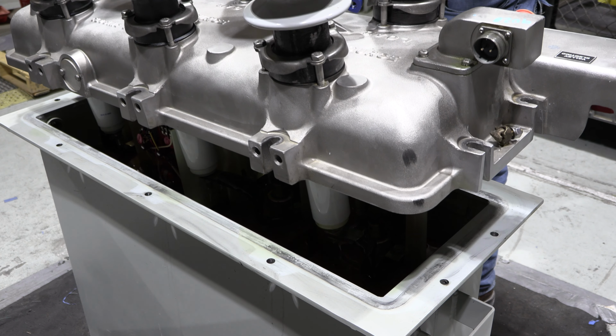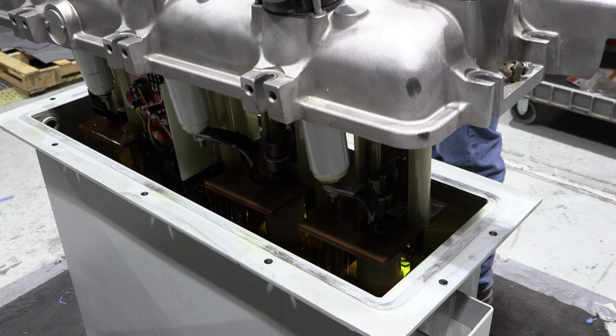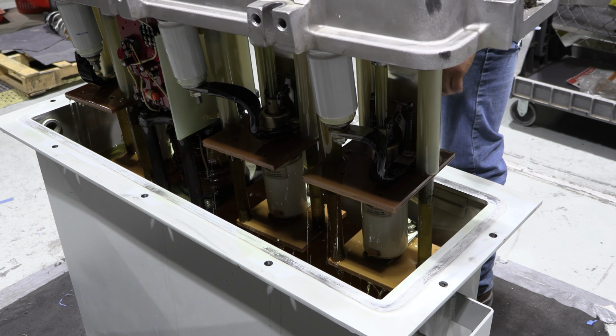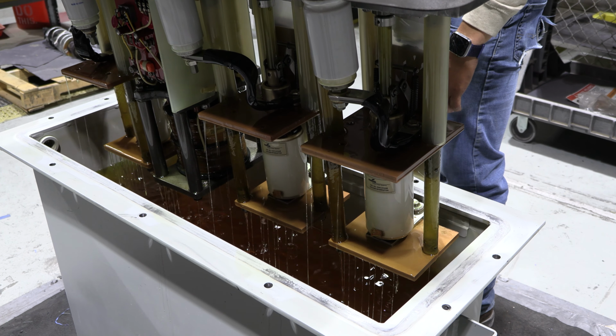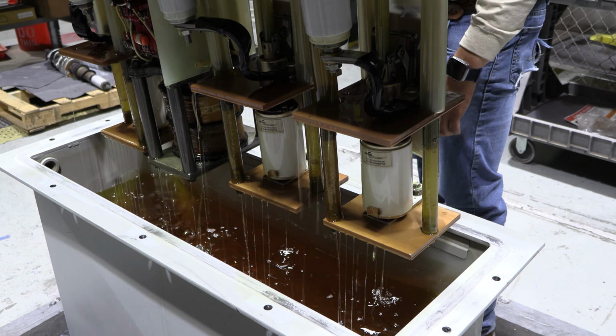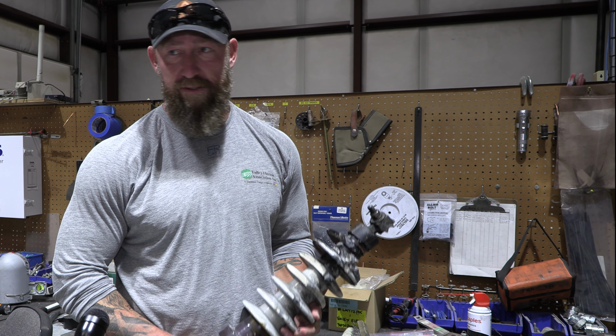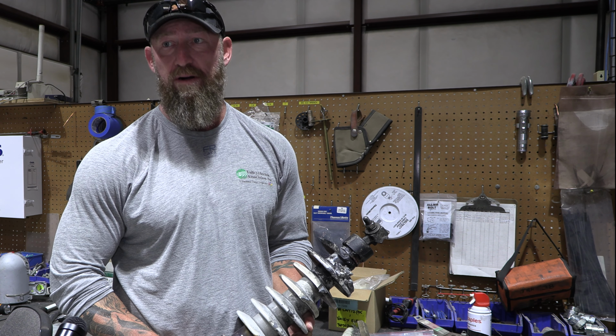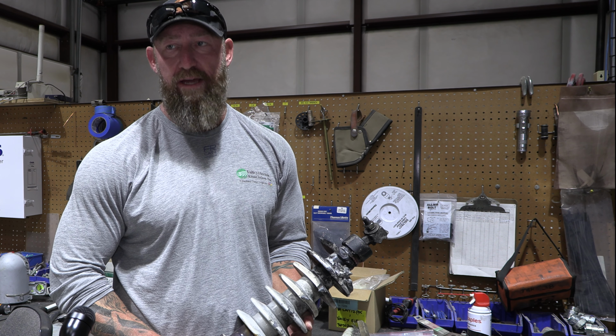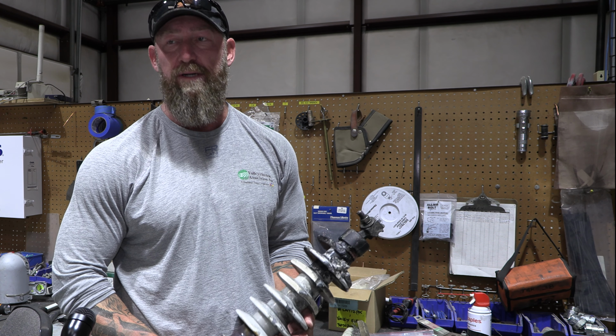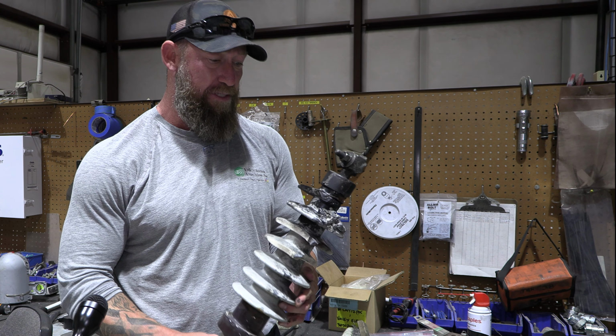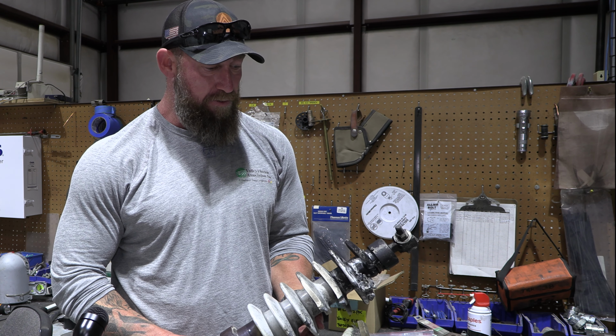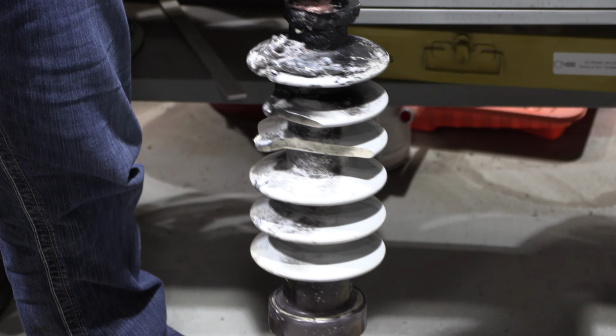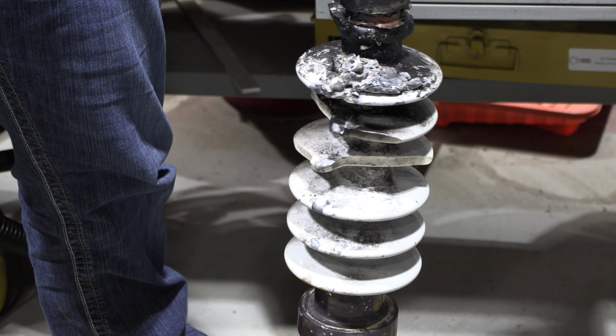So a recloser is a protective device that gets mounted on the lines. When it detects a fault on the line, it will measure that through a relay and tell the recloser to open. A lot of our problems here on our system are bird related, so many of the outages are caused by birds. You'll see this was caused by a bird on a recloser, so we've had to replace the bushings on this recloser to get it back in service.